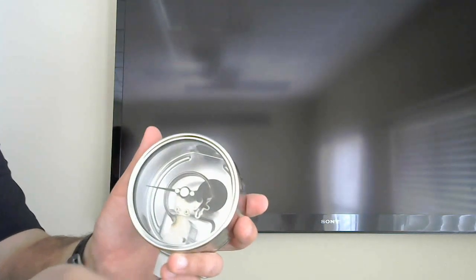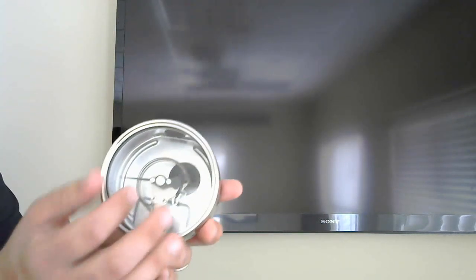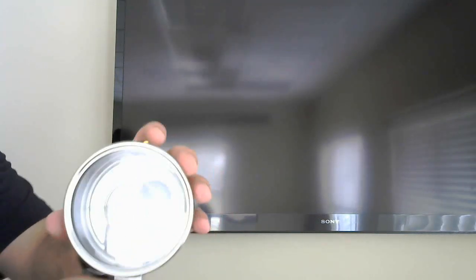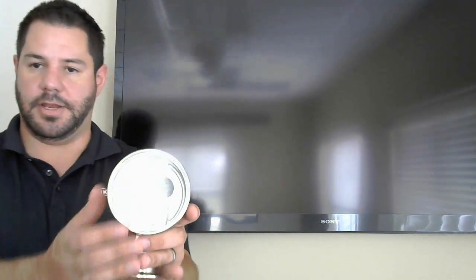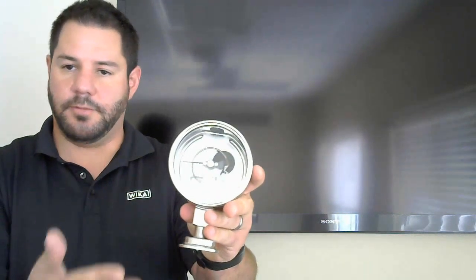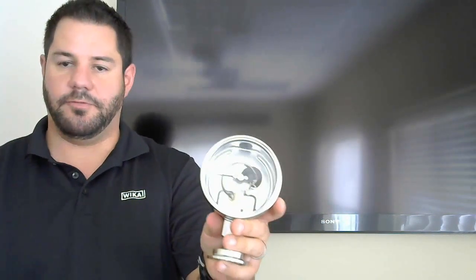Second, we use a smaller Bourdon tube than the competition typically uses. In both our 4-inch and 2.5-inch gauges, we use the same 2.5-inch Bourdon tube, and we're still able to keep the same accuracy level. That means less fill fluid in the tube. Fill fluid getting into product, although FDA approved, is still heavily frowned upon in this industry. This is a very good gauge with great selling features - it can go into food, pharmaceutical, brewery, any sanitary industry, and will be used in the process.